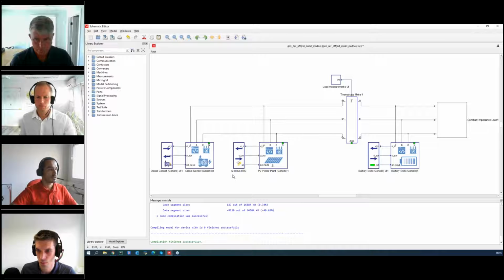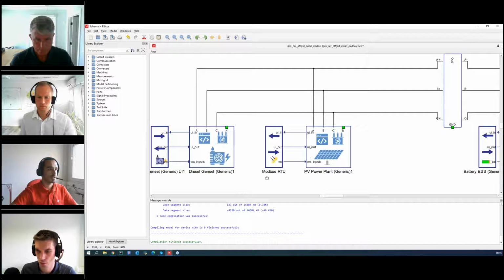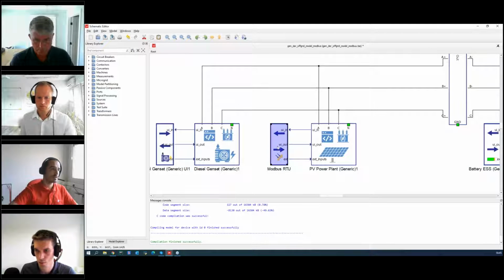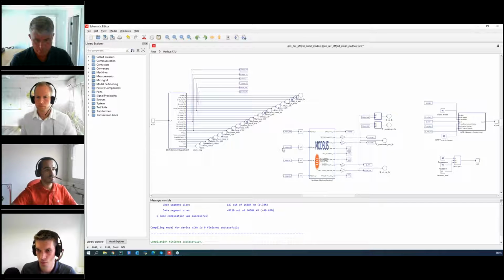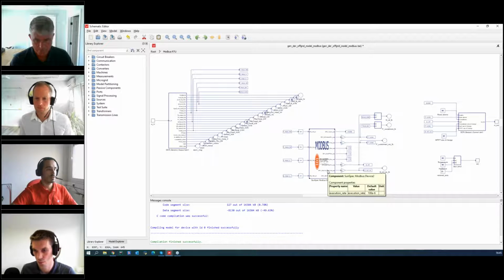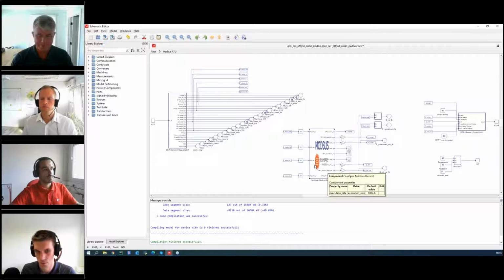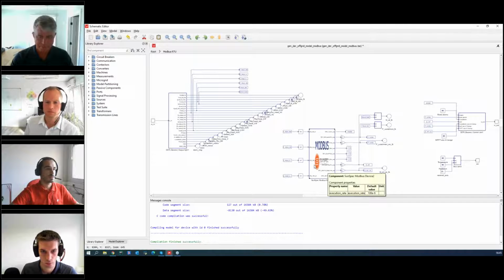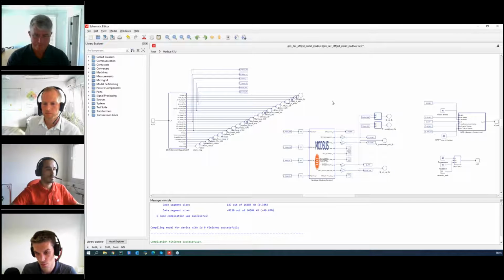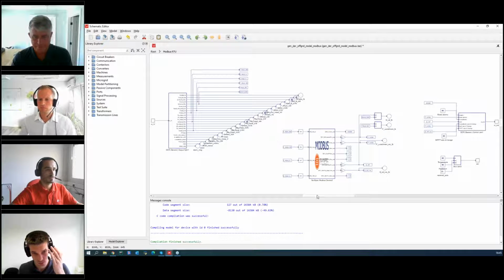I will show you an example of how we did it. We actually inserted a Modbus Sunspec server inside the UI component. This is a PV UI block, and this PV power plant will actually be controlled directly from the Modbus. The idea with this UI component is that you can easily insert the communication protocol that you want.